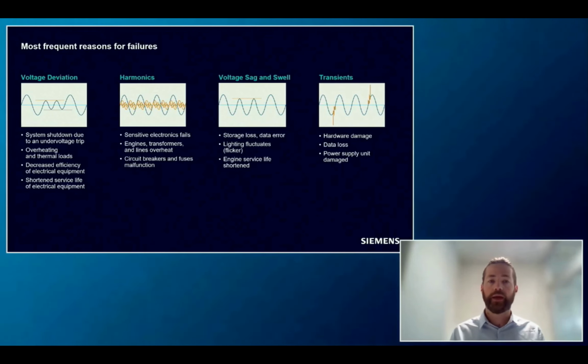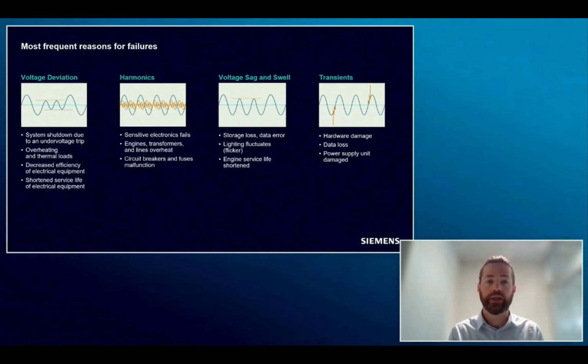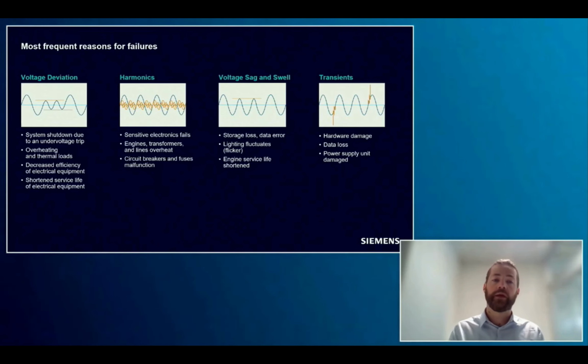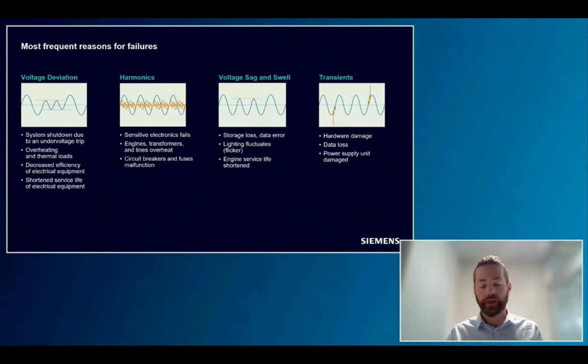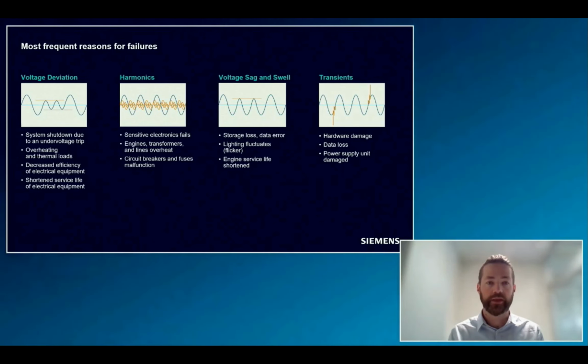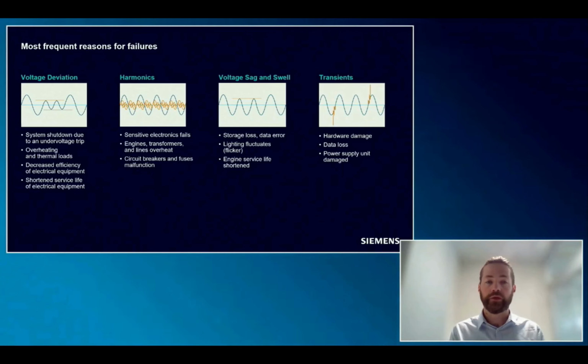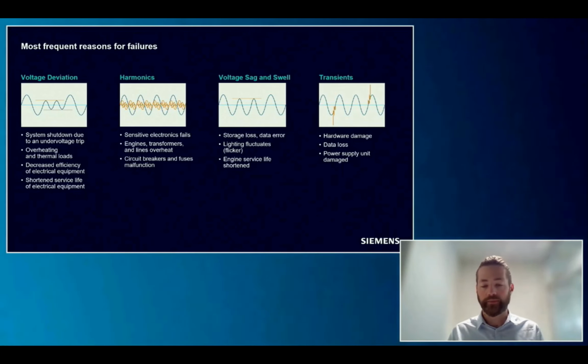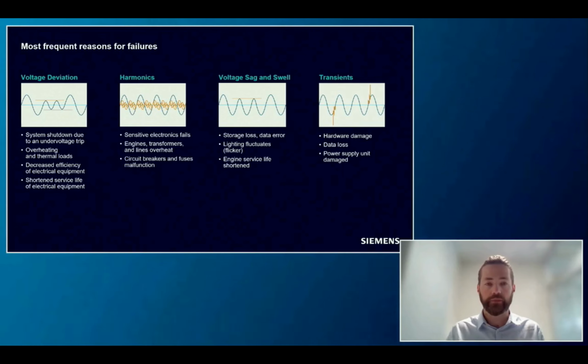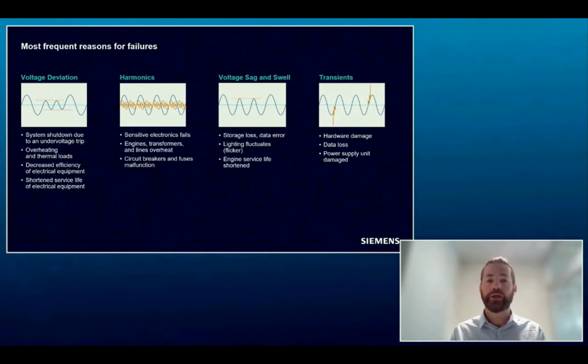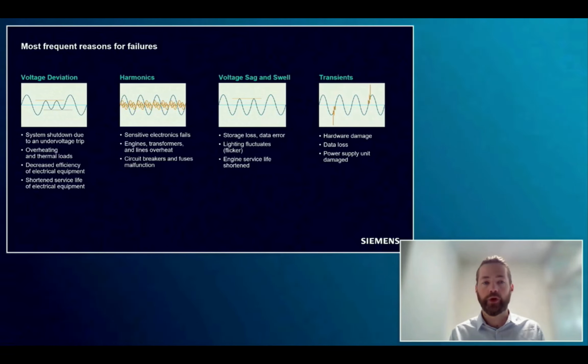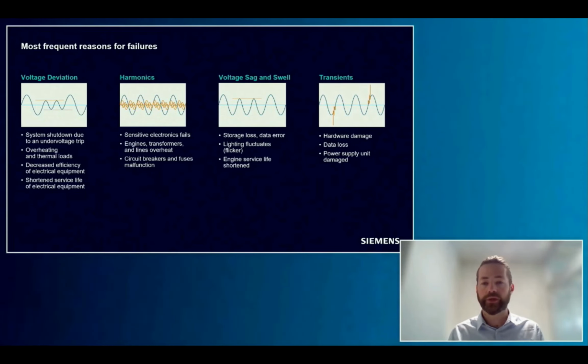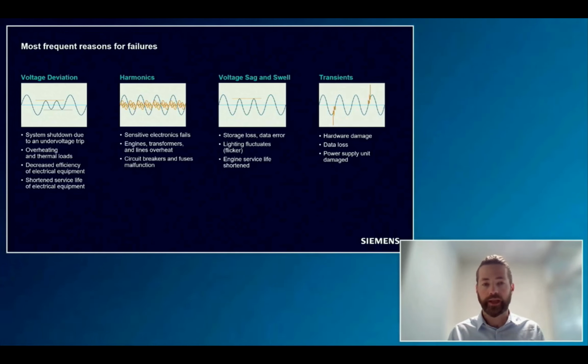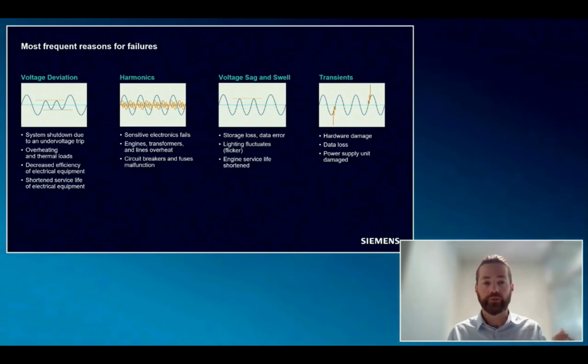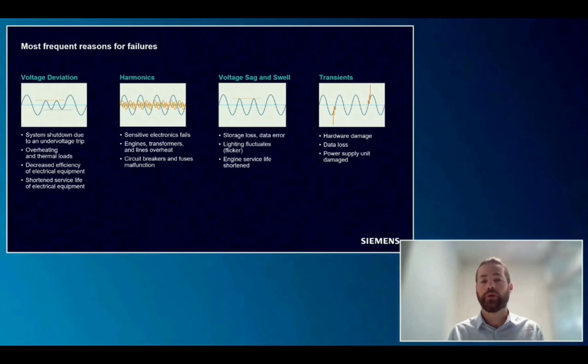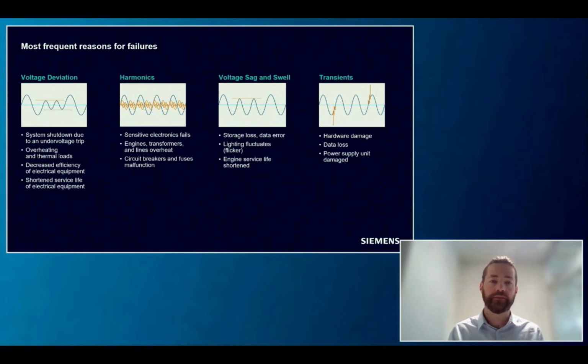Then harmonics, for example, can have an influence on sensitive electronic components, processing units, and such things, where this might lead to failures, to downtimes, to devices being reset, or engines and transformers overheating because of those harmonics being introduced into your system by your electrical power distribution. Certain breakers or fuses would not work in the correct way, or might malfunction.